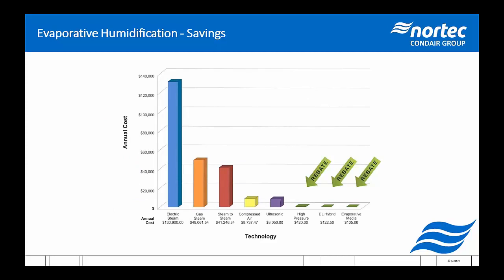So when we talk about the actual costs, again, we're looking at the electric steam, gas steam, steam to steam, and then the compressed air, ultrasonic, and the rest of the evaporative technologies. Now these costs don't include preheat or reheat, so I have to always point that out. But the three on the end, the high pressure, the DL system, the evaporative media system, typically can be applied for rebates and typically get rebates back from utilities for electric reduction. And that can even be from compressed air or ultrasonic humidification.